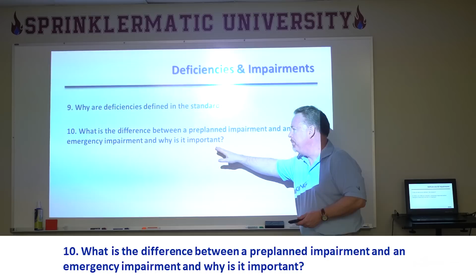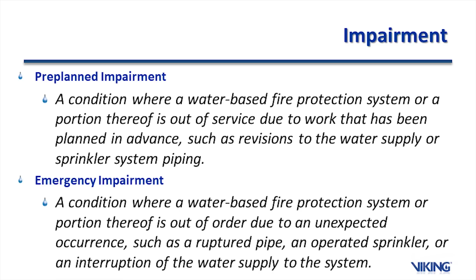Let's start with impairment, since a definition of impairment has been in the standard since the 1992 edition. Basically, it's a condition where the system, or a portion of it, is out of service and will not operate, due to work that has been planned, such as revisions to the water supply piping. So we're taking the system out of service, it will not operate, we're closing a valve.